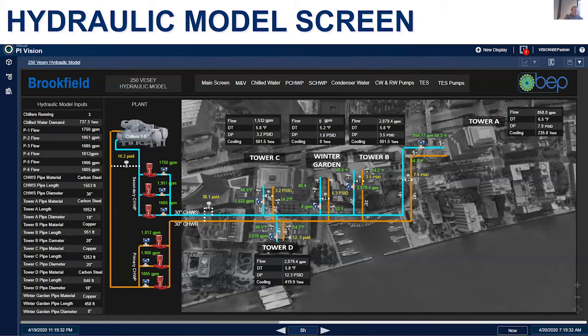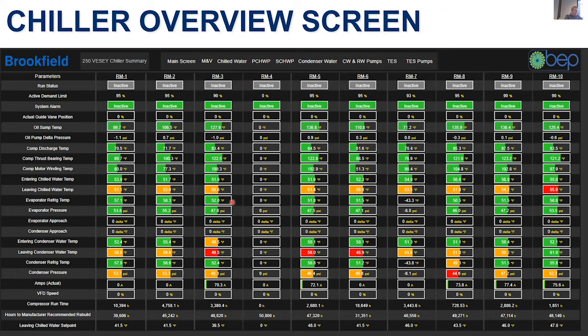This is a fun screen for me because I'm a chiller nerd, but pretty boring for a lot of other people. But what I like about this screen is that at a glance I can see all my machines and see if something's wrong instantaneously. Thrust bearing temperatures, stuff like that, are going to alert me. Even the chiller panel doesn't really give me a preemptive warning when the thrust bearing temperature or motor winding temperature is getting too high. So it gives the operators one glance to say, hey, everything looks good, on a value that you don't really know is too high until there's catastrophic failure.